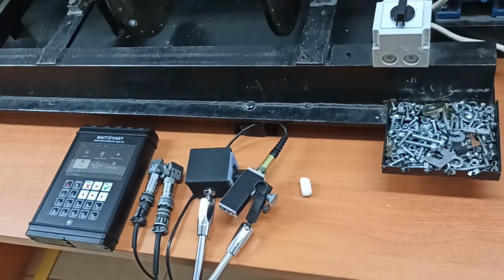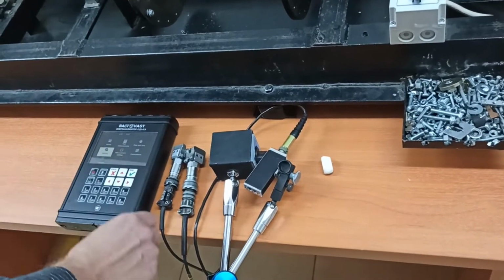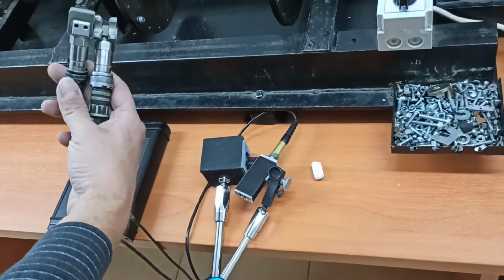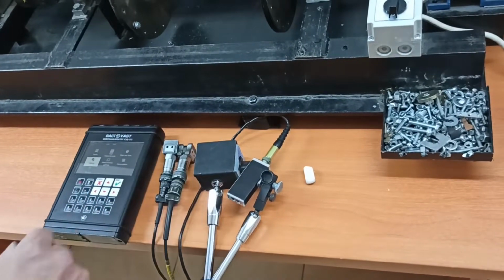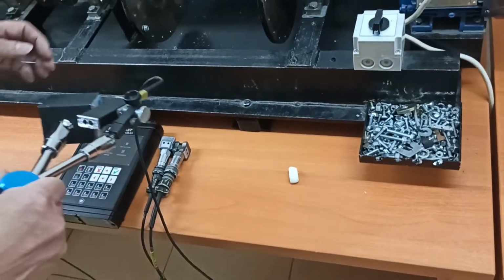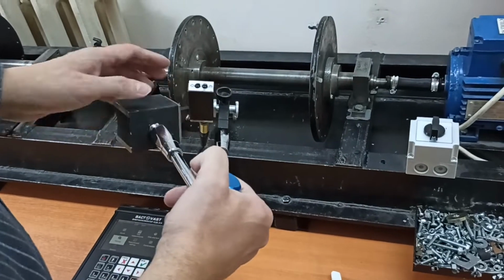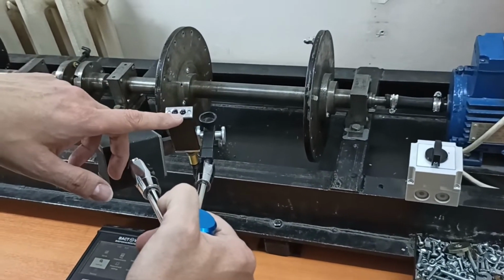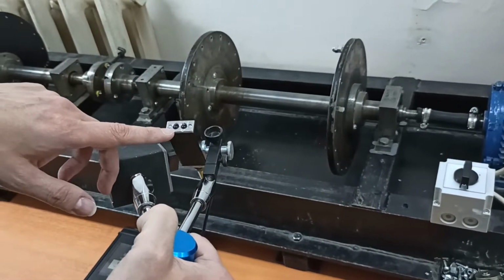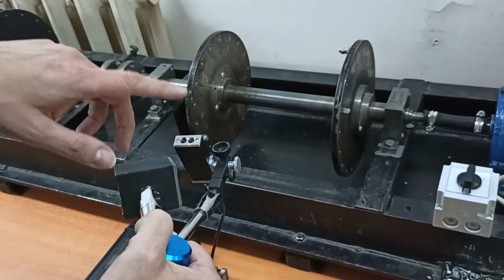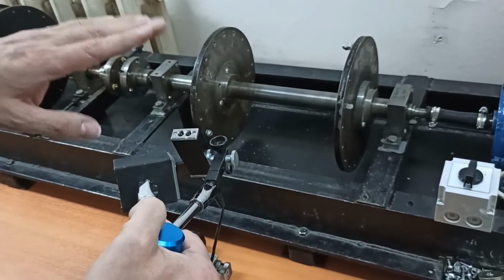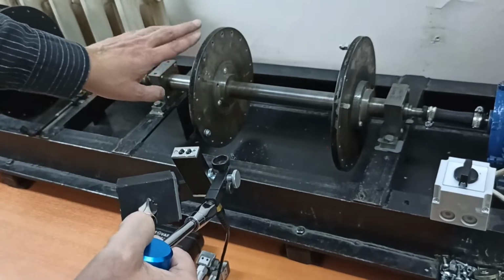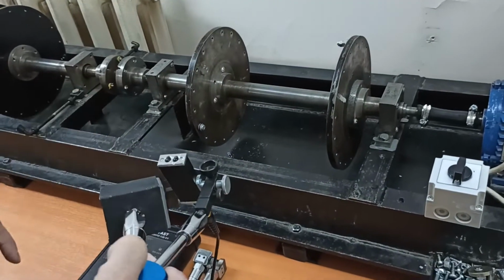With the data collector or vibration analyzer DC-23 we have two accelerometers for the two channels, and a tacho probe. The tacho probe here is a photo tacho probe. It has two infrared diodes, one emitting, one receiving. So one emits infrared, it reflects from the machine and is received by the other one.